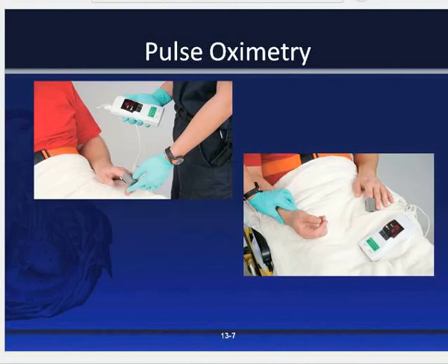To use a pulse oximeter, start by making sure there is no dirt or obstruction on the oximeter's red light. If dirt is present, remove it and clean the device before putting it on the patient. Usually an alcohol prep will work just fine. Clean the tissue on the patient to which the pulse oximeter will be attached, such as a fingertip or earlobe. If the patient's fingertip is used, remove any dark or metallic nail polish if present. Attach the pulse oximeter to the patient.